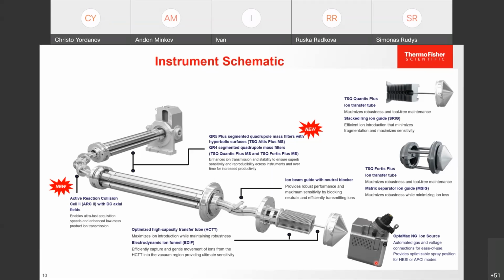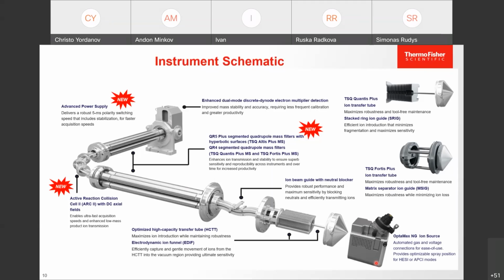An improved collision cell with higher speed and improved low mass product ion transmission is available on TSQ Plus. An advanced power supply means we have very fast polarity switching of 5 milliseconds, which includes also stabilization time, which really speeds up analysis. So these are the schematics of the TSQ, what is inside the box.